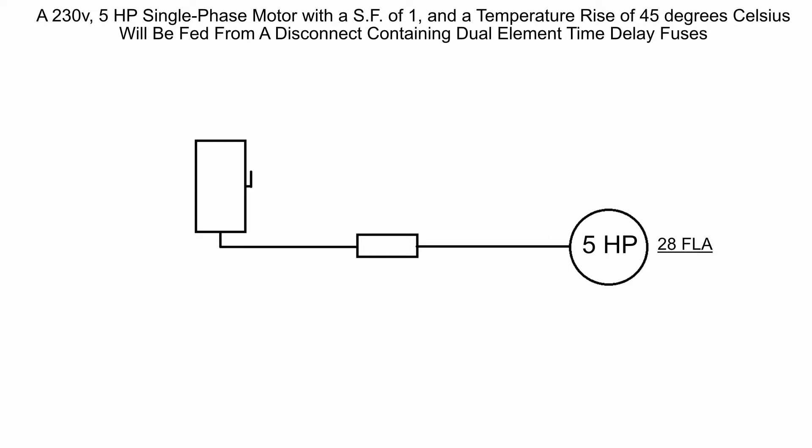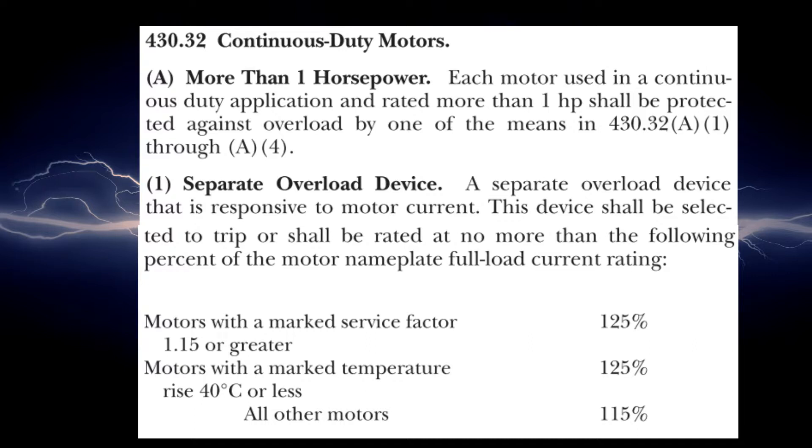To do the thermal overloads, that's the first step we need to look over to 430.32. This is the continuous motor duty motors that's going to tell you what type of devices that you need. If we look at 430.32(A)(1), it's going to say a separate overload device that is responsive to motor current shall be selected to trip or shall be rated at no more than the following percent of the motor nameplate full load current rating. We don't have the full load current rating of the nameplate so we're going to use the full load amps.